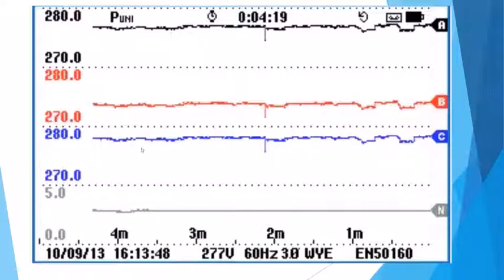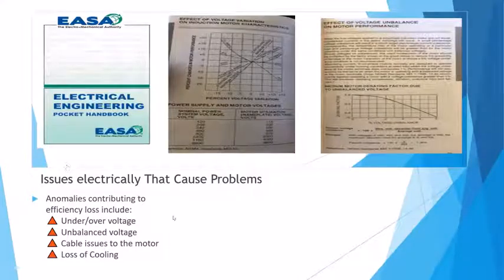Again, back to that Fluke meter, your line-to-line voltage between A, B, and C, where is it? Is it within tolerances? Is it where we want it to be? It also picks up voltage spikes, and you can record over time. Again, let's recap the failure analysis information: was it originally designed right? Is it set at the right efficiency point of the motor compared to what our voltage of our power is? So we have under voltage, over voltage, and unbalanced voltages. And I'll go a little bit into cabling issues.